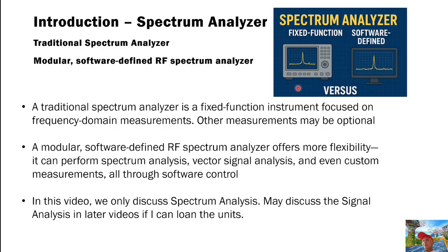In the early days, the spectrum analyzer was only the traditional one. That means you buy the whole unit with the monitor and the user interface here. Now you can have the so-called modular software-defined spectrum analyzer. That means you only purchase some of the hardware, for example, a PXI module, which you can get from Keysight or National Instruments or other vendors, maybe such as MVIT Technologies. Then you install the software on your computer.